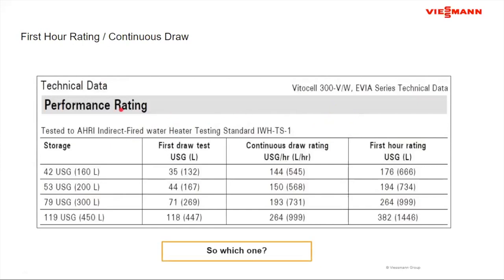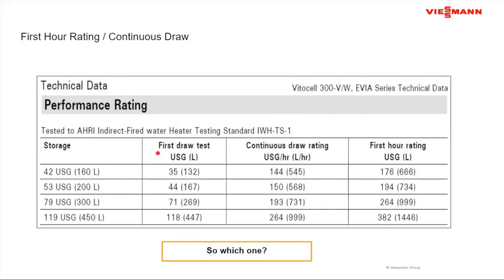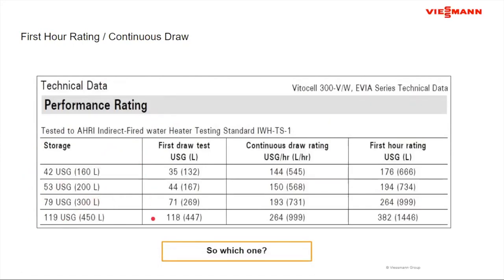So here are some AHRI numbers for various water heaters from 42 to 119 gallons. The first draw test is simply how much hot water is available from the tank without any recovery. For instance, this 42 gallon tank will give me about 35 gallons of usable hot water. That is above the 75% number, because 75% is the generic number the industry usually uses, while this is product specific. Look at the 119 gallon tank: under the first draw test conditions, I can get 118 gallons out of it. More than 99% of that is usable hot water.